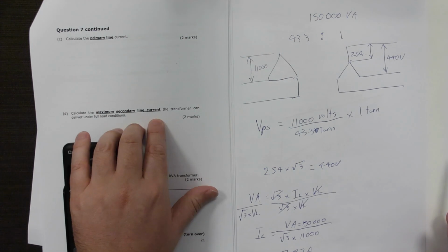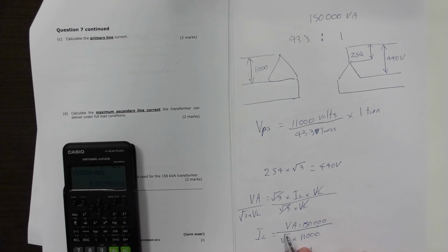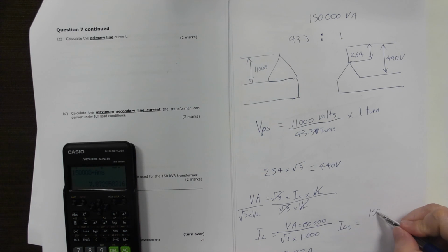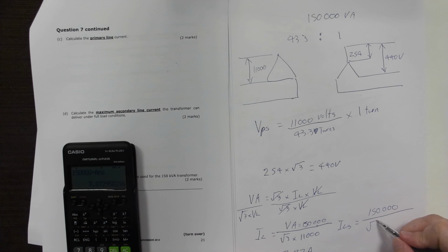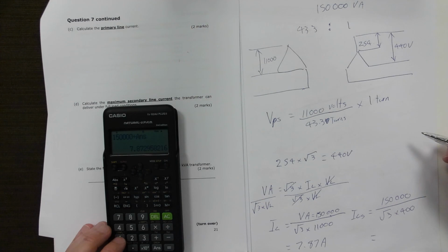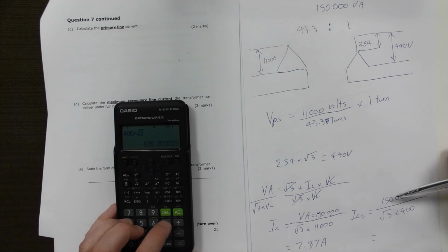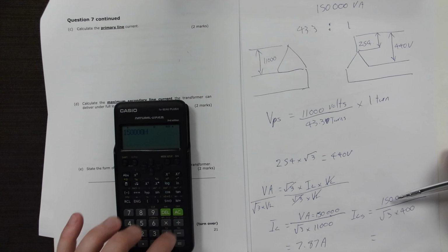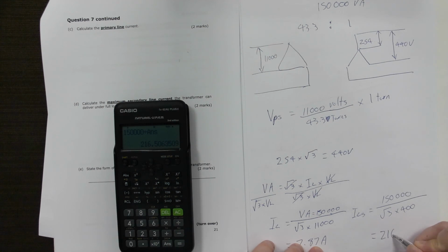Now thereafter the maximum secondary line current. We do exactly the same formula. The only thing that changes is instead of being 11,000, it's going to be 440. So I line secondary equals 150,000 over root 3 times 400 equals. So we go 400 times by square root of 3, just putting it in reverse because it's faster on the calculator. Then 150,000 divided by answer, and we get 216.51 amps.